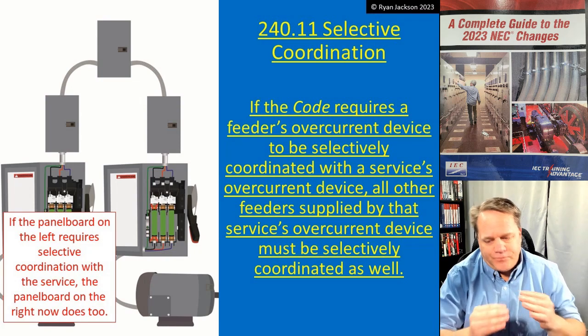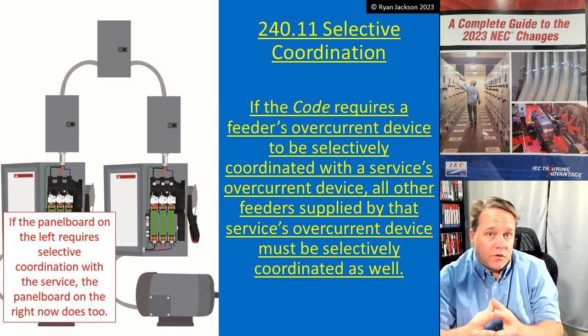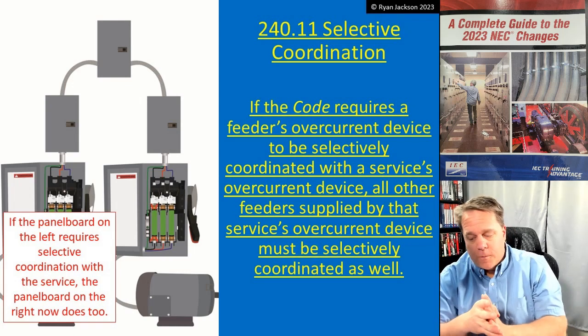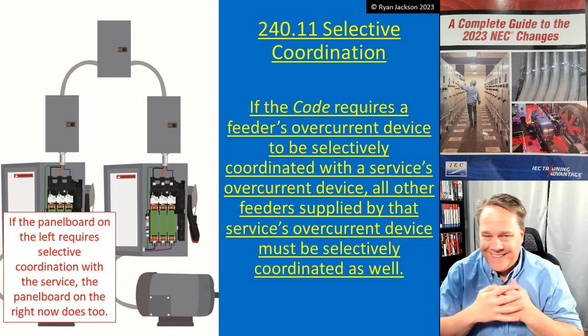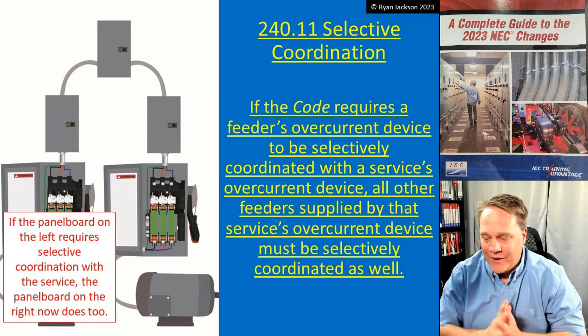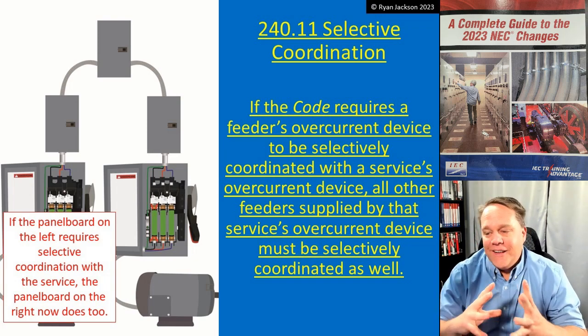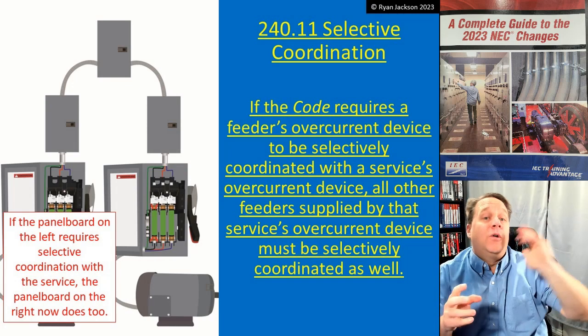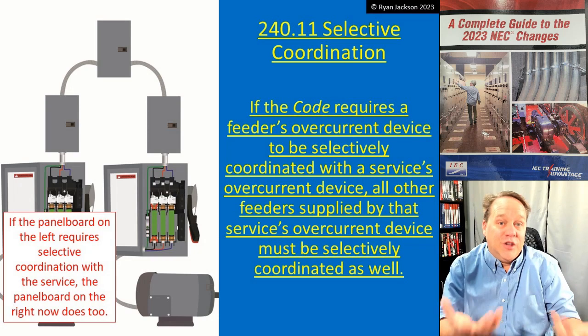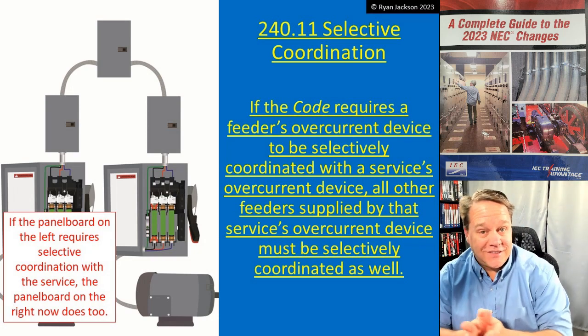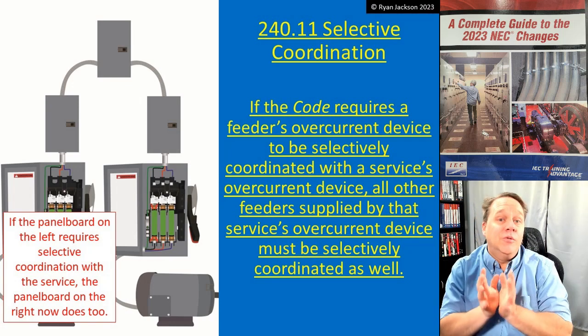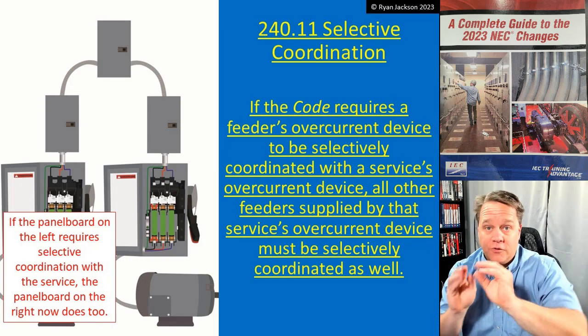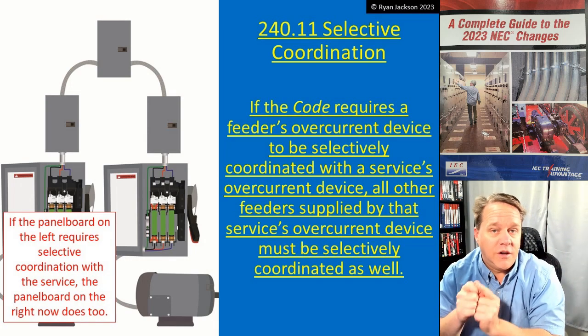Selective coordination means that the fuse or circuit breaker directly upstream of a fault is the only breaker or fuse that opens. In a commercial building, it's not unheard of to have an incident where a 20-amp ground fault or short circuit should have tripped the 20-amp breaker but instead tripped the 400-amp main outside, or the ground fault protection device on the 2000-amp main. That is the antithesis of selective coordination. In a selectively coordinated system, only the circuit breaker or fuse directly upstream of the fault opens.